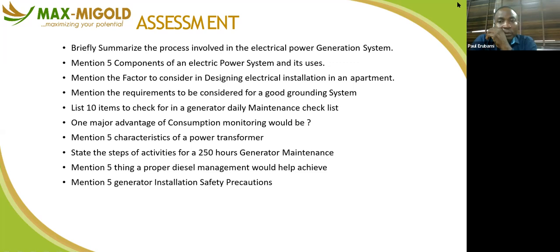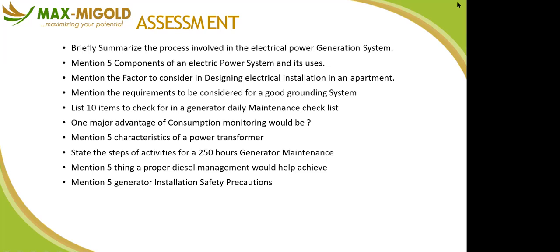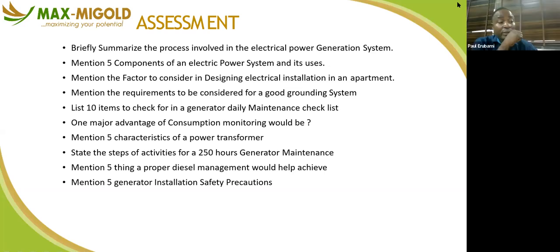300? I didn't get you. Hello. Yeah. Continue. So what I'm saying is, what I know is a 100 kVA generator produces 80 kilowatts. So somebody with 200 kilowatts should be using like a 300 kVA generator, because that would be like 240, I guess. I don't know if that's right. That's 250. It will give up to 250 kilowatts.